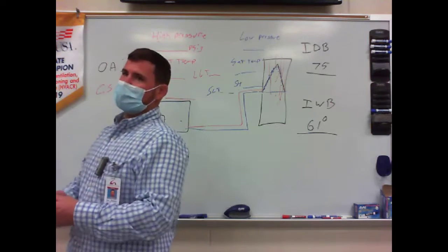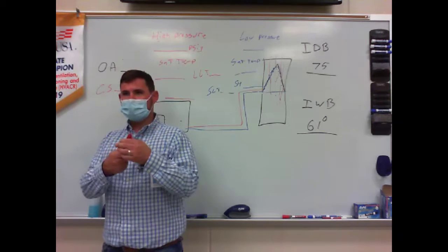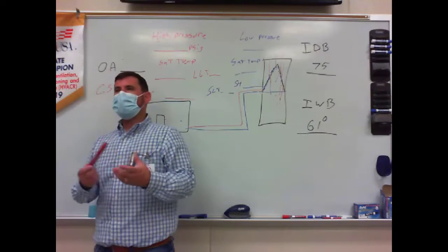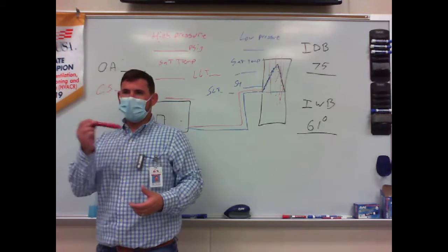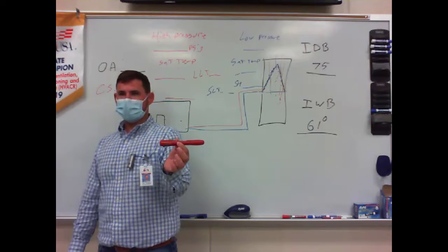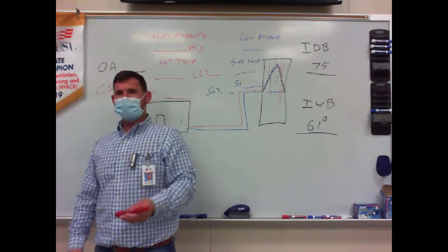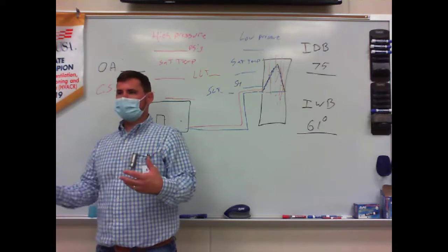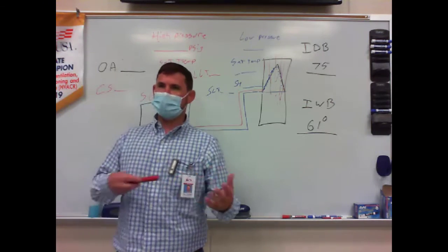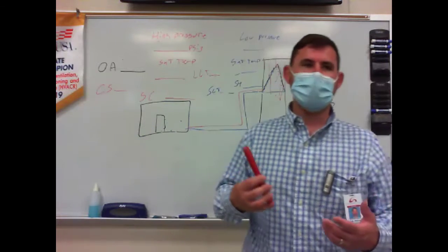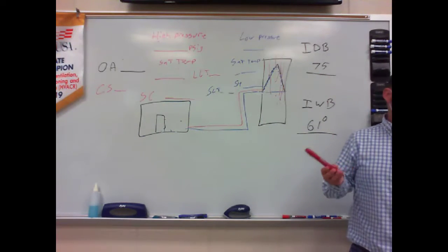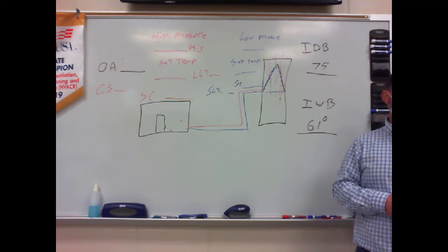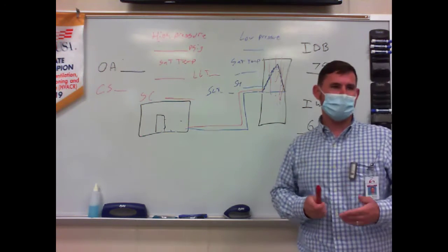The wet bulb, you're right, we wet a little cloth of some kind and wrap it around our temperature sensor and we leave it there. Now it's a lot more accurate to buy at least the little digital pocket psychrometers that are calibrated to pick that stuff up. Because with water, you don't know if it's cold, is it warmer, is it distilled, is it going to be an accurate reading, do you have enough air going across it to give a good accurate wet bulb? But I find it's actually pretty accurate, close enough for us to be able to use our charts and things to see if we're adjusted where we need to be.